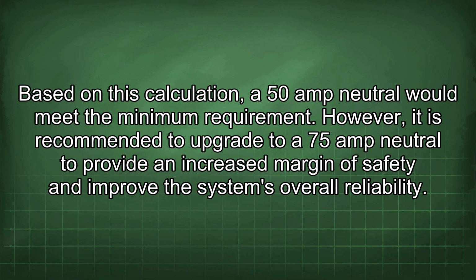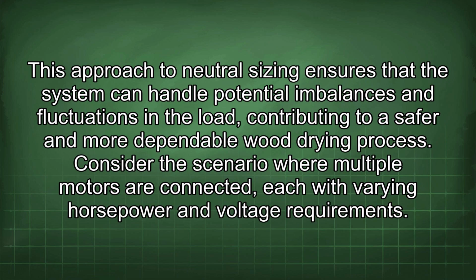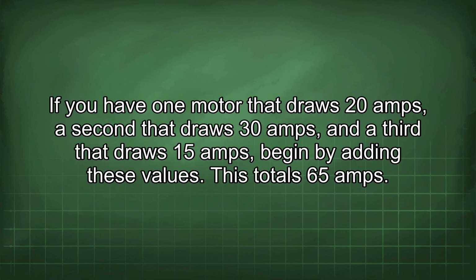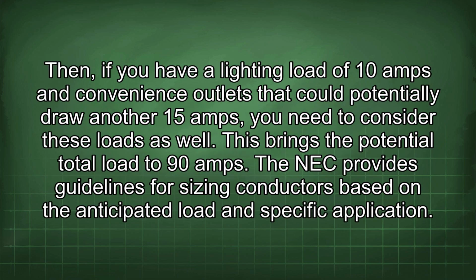This approach to neutral sizing ensures that the system can handle potential imbalances and fluctuations in the load, contributing to a safer and more dependable wood drying process. Consider the scenario where multiple motors are connected, each with varying horsepower and voltage requirements. If you have one motor that draws 20 amps, a second that draws 30 amps, and a third that draws 15 amps, begin by adding these values. This totals 65 amps. Then, if you have a lighting load of 10 amps and convenience outlets that could potentially draw another 15 amps, you need to consider these loads as well. This brings the potential total load to 90 amps.